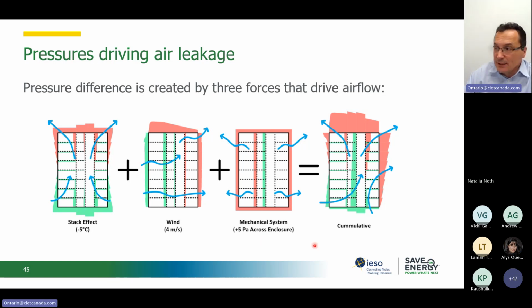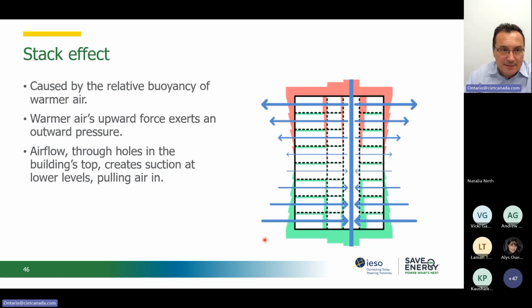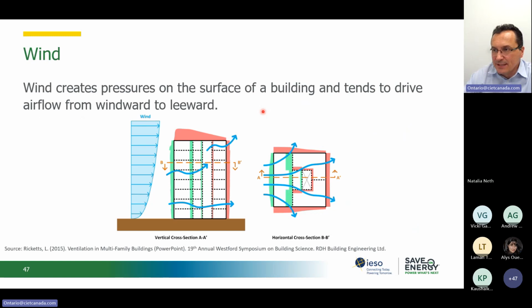So what we see in our buildings is a cumulative effect of these three: the stack effect plus the wind plus the unbalanced mechanical systems. So that air is basically introduced at the bottom of the building. It has to be conditioned because now it's in the space, and then gets exhausted at the top of the building, removing a significant amount of heat, or a significant amount of energy that needs to be added back into the building for comfort. So the wind effect, as you see here, increases typically with the height of the building. It's present on higher elevations of the building.